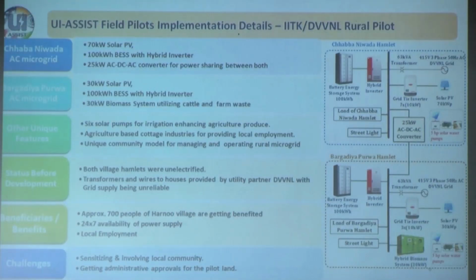So this is the architecture. In Bargadia Purva we have 100 kilowatt hour of lithium ion battery energy storage, connected to the local distribution system using a hybrid inverter. We also have 30 kilowatt of biomass and 30 kilowatt of solar system there, so in fact they have 60 kilowatt of energy supply when the grid is not available.